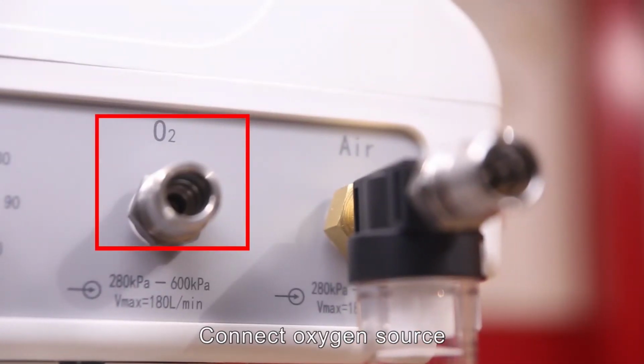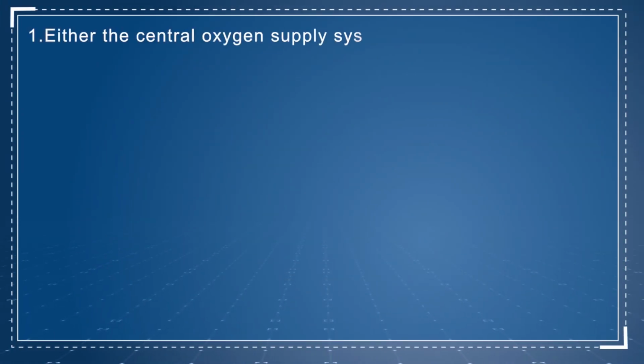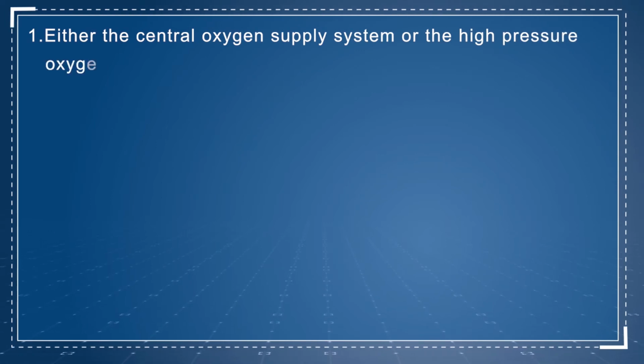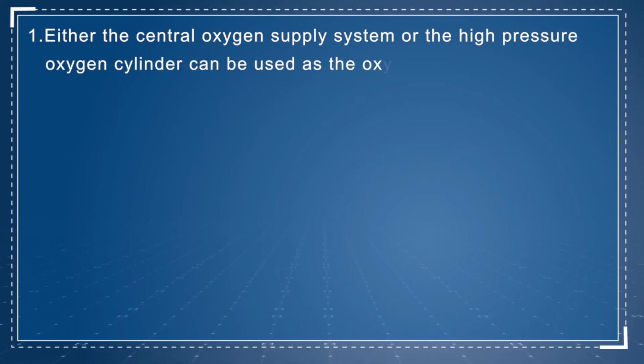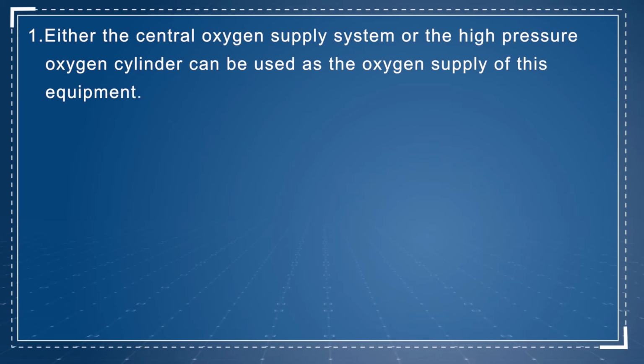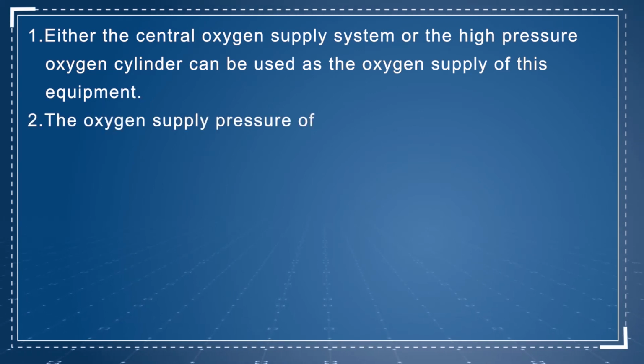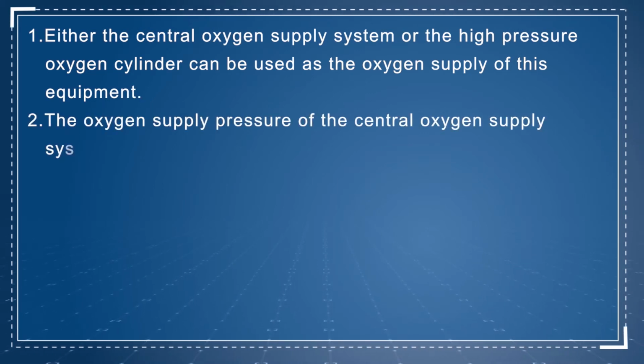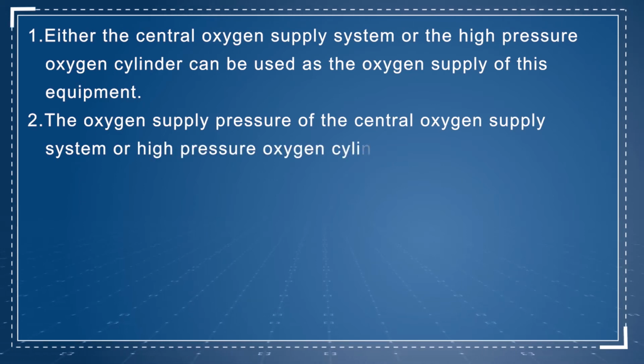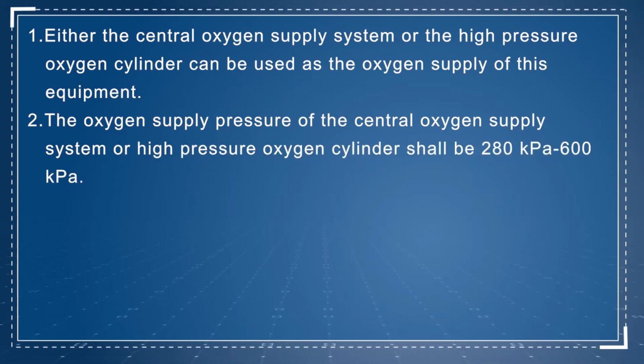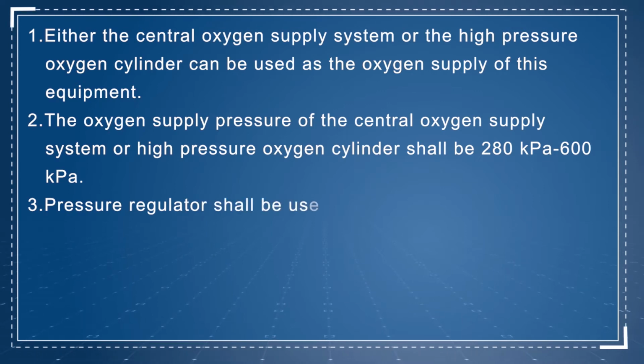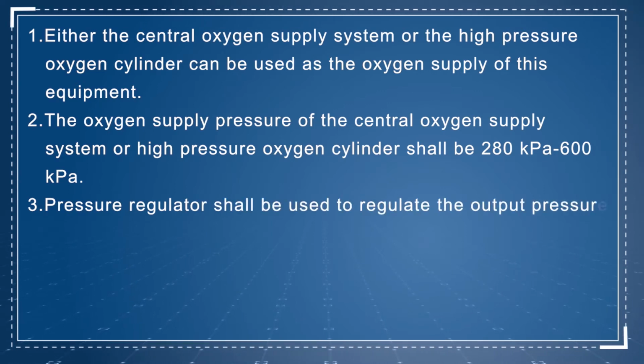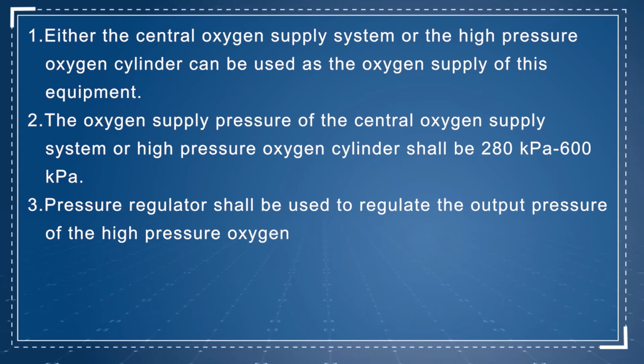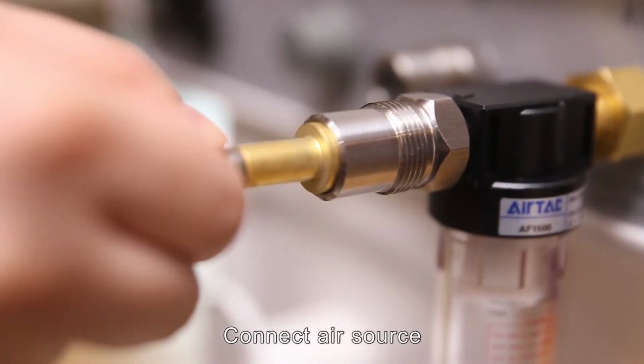Connect oxygen source. 1. Either the central oxygen supply system or the high-pressure oxygen cylinder can be used as the oxygen supply of this equipment. 2. The oxygen supply pressure of the central oxygen supply system or high-pressure oxygen cylinder shall be 280 kPa to 600 kPa. 3. A pressure regulator shall be used to regulate the output pressure of the high-pressure oxygen cylinder. Connect air source.